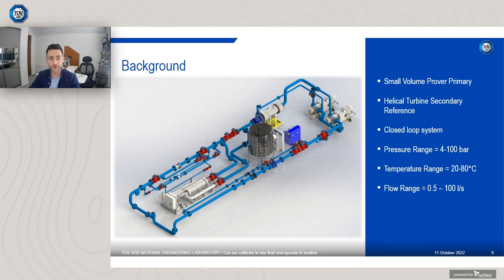The flow range operates from 0.5 to 100 litres per second. And crucially, the measurement uncertainty for mass and volume is 0.08%. Now you may know, we calibrate a lot of Coriolis meters, which are mass-based devices, and our references are volumetric. We have a volumetric prover and a volumetric reference helical turbine system. That means that density is an extremely important component. So we have characterised our fluids with respect to temperature and pressure across the entire operating range and have very stable fluid properties which we monitor, and we have a very low measurement uncertainty for the density. That allows us to then calibrate with respect to both mass and volume for an uncertainty of 0.08% at the 95% confidence level.